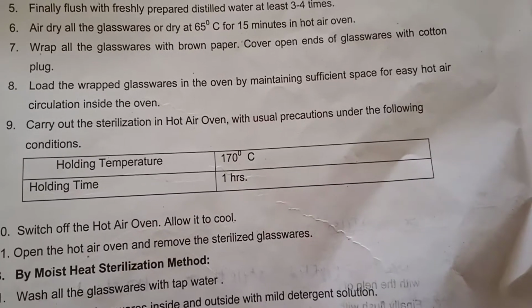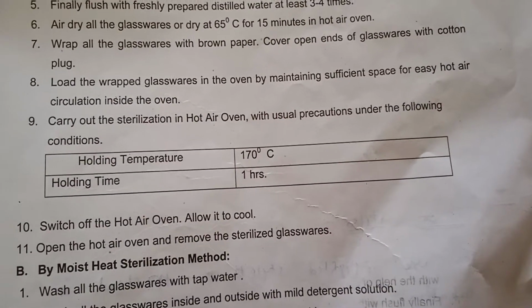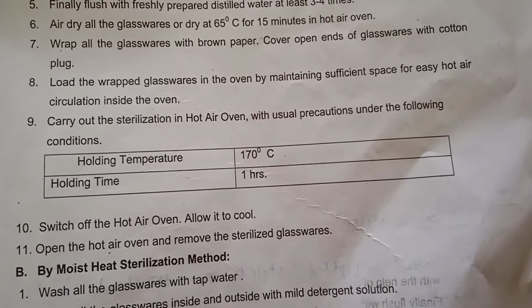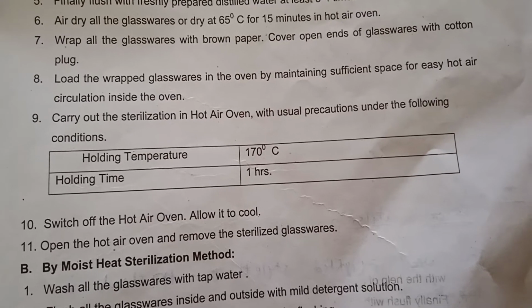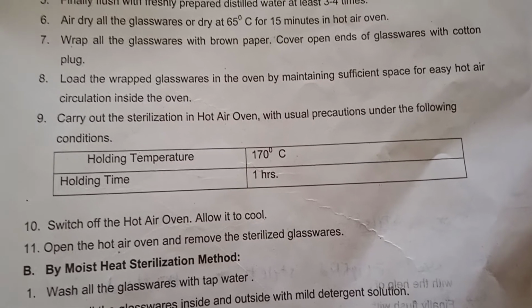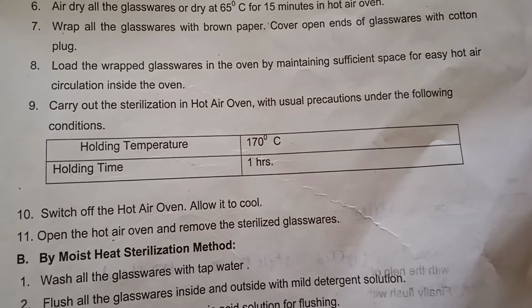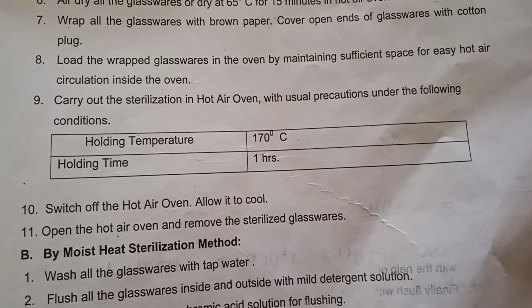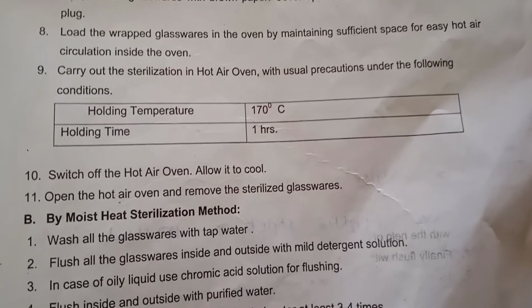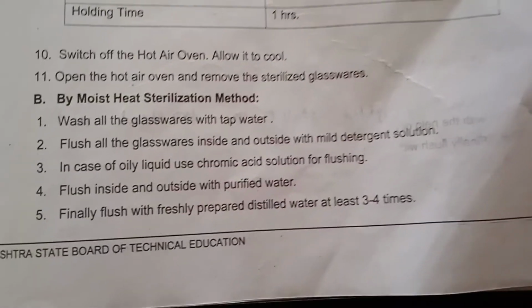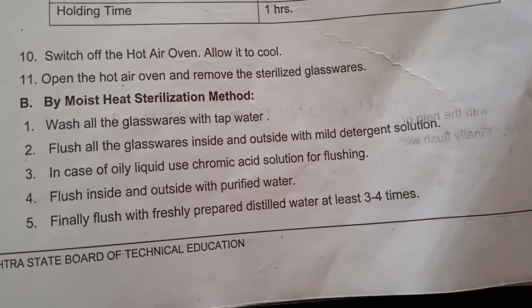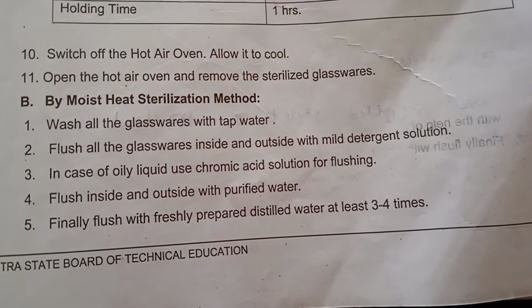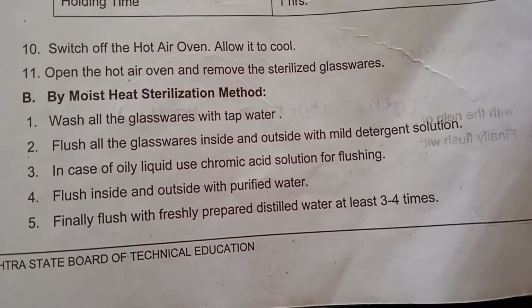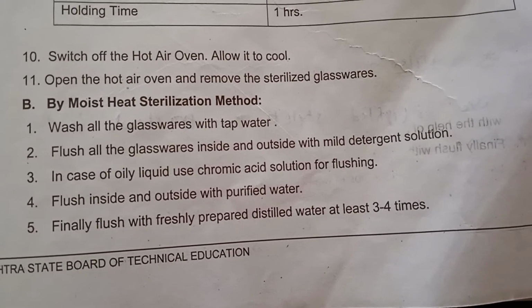Carry out the sterilization in the hot air oven with the usual precautions. You have to use a temperature of 170 degrees Celsius, and you have to sterilize it for 1 hour. After sterilization, you have to switch off the hot air oven, allow it to cool, and then store it in the sterile area only. The second method for sterilization of the glasswares is the same as that of the needles, that is, moist sterilization or autoclaving.